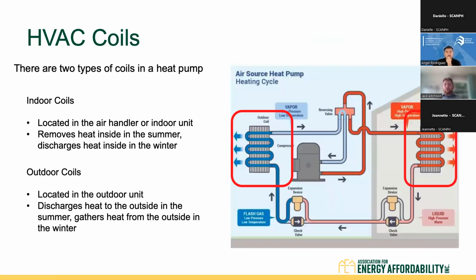So moving on to HVAC coils. This is sort of the last thing that you need to be considerate of when maintaining heat pump HVAC. We have two types of coils in a heat pump. We have our indoor coil, which is located in the air handler or indoor unit, removes heat inside in the summer, discharges heat inside in the winter. Ultimately, our coils are basically all of the action of a heat pump. That's what's going to be transferring heat into the unit. That's what's going to be transferring heat out of the unit in cooling mode. And it's going to be sent out to the outdoor coil that's either going to be pulling heat from the outside to transfer into the unit during heating mode, or just dispensing heat that was from the inside in cooling mode.